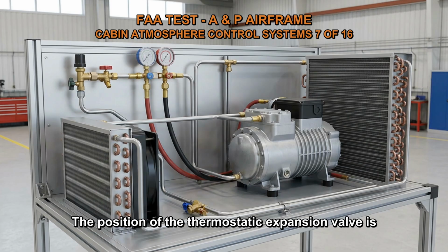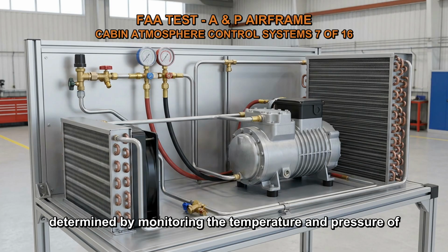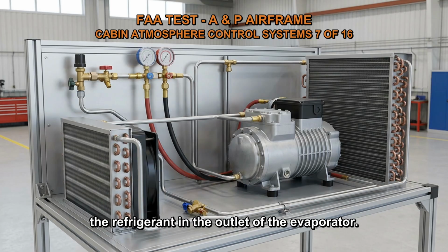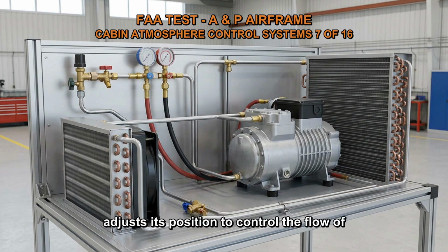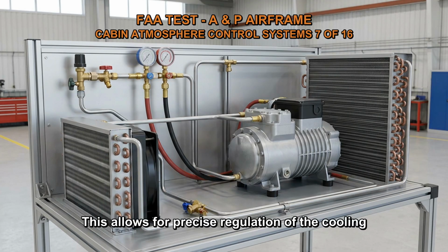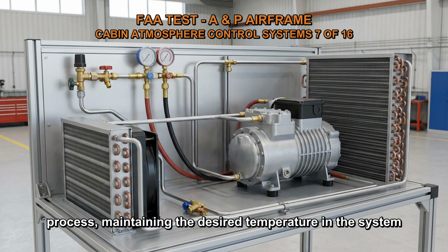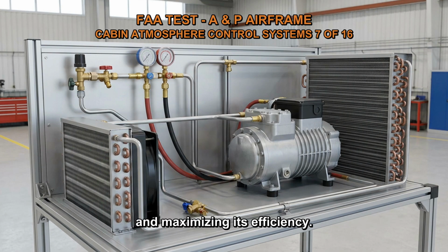The position of the thermostatic expansion valve is determined by monitoring the temperature and pressure of the refrigerant in the outlet of the evaporator. As the temperature and pressure change, the valve adjusts its position to control the flow of refrigerant accordingly. This allows for precise regulation of the cooling process, maintaining the desired temperature in the system and maximizing its efficiency.